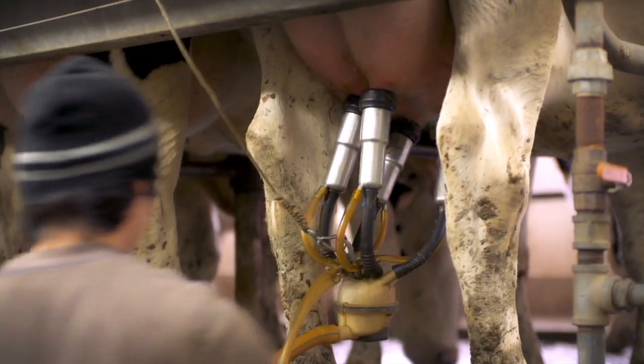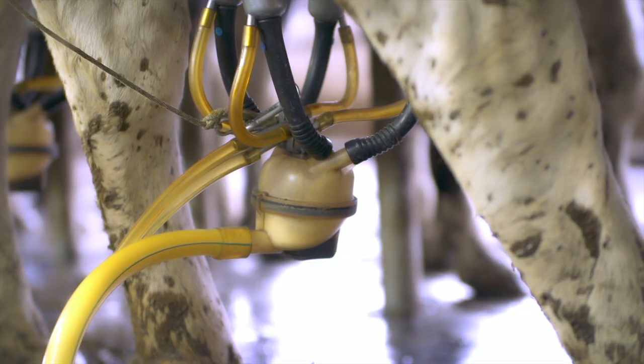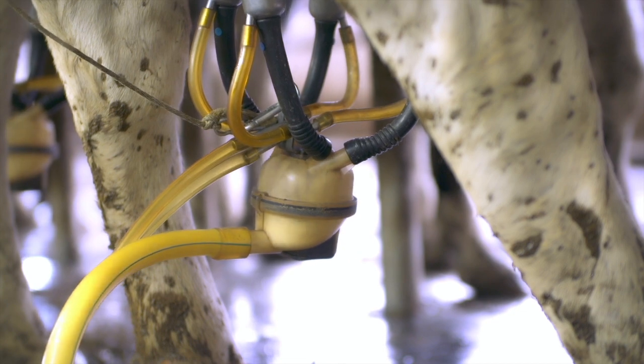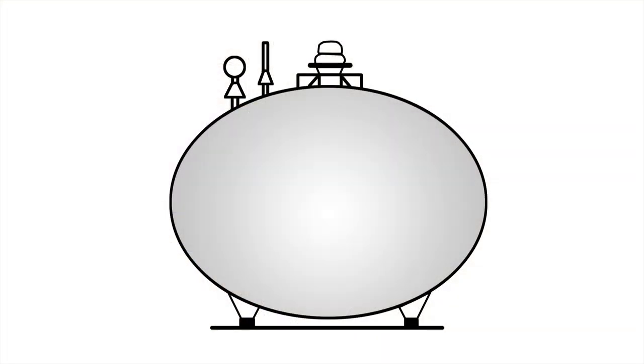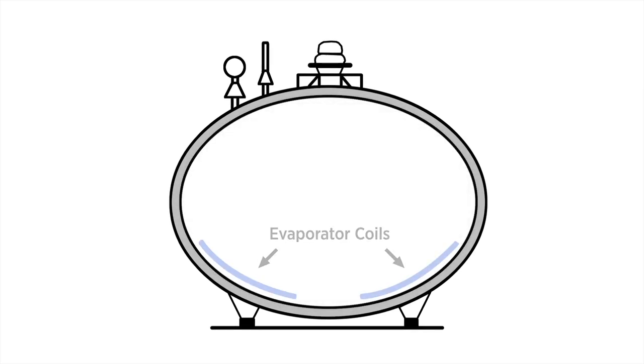Milk leaves the cow at around 101 degrees and must be quickly cooled to around 38 degrees using the bulk tank's refrigeration system. The standard compressor-based system circulates liquid refrigerant through evaporator coils in the bulk tank.